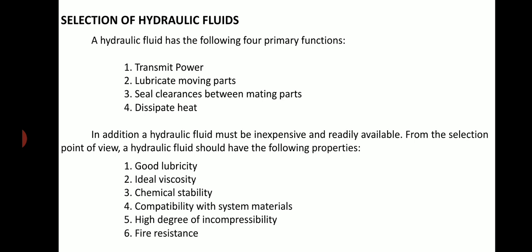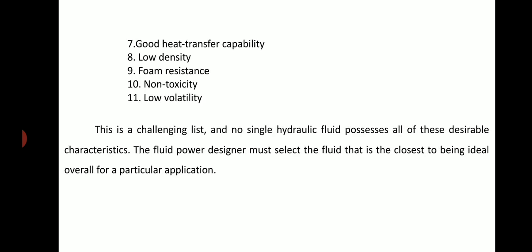From the selection point of view, a hydraulic fluid should have the following properties: good lubricity, ideal viscosity, chemical stability, compatibility with system materials, high degree of incompressibility, fire resistance, good heat transfer capability, low density, foam resistance, non-toxicity, and low volatility. This is a challenging list and no single hydraulic fluid possesses all of these desirable characteristics. The fluid power designer must select the fluid that is the closest to being ideal overall for a particular application.